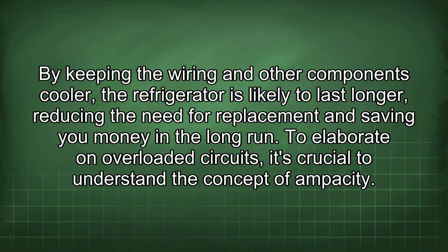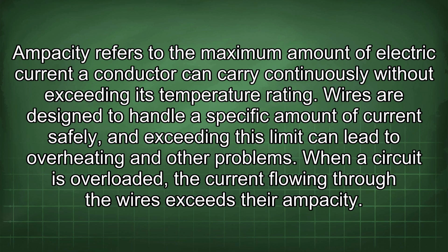To elaborate on overloaded circuits, it's crucial to understand the concept of ampacity. Ampacity refers to the maximum amount of electric current a conductor can carry continuously without exceeding its temperature rating. Wires are designed to handle a specific amount of current safely, and exceeding this limit can lead to overheating and other problems. When a circuit is overloaded, the current flowing through the wires exceeds their ampacity.